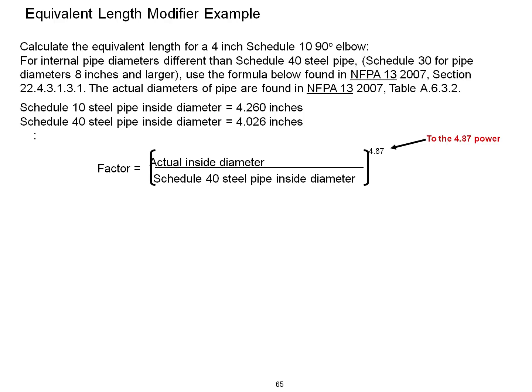This slide is for an equivalent length modifier example. Calculate the equivalent length for a 4 inch Schedule 10 90 degree elbow. For internal pipe diameters different than Schedule 40 steel pipe, Schedule 30 for pipe diameters 8 inch and larger, use the formula below found in NFPA 13, Section 22.4.3.1.3.1.